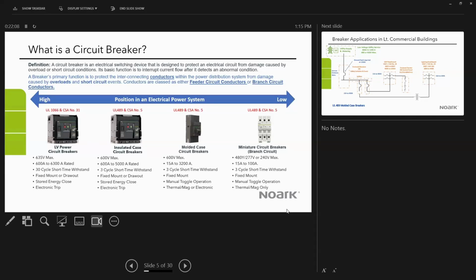number 31 in Canada. If I move on to the next breaker to the right, it looks very much like a low voltage circuit breaker. And in fact, it is the same construction, but it's a breaker that's been tested to the molded case breaker standards, which is UL 489 and CSA number 5. And the reason for having the same type of breaker with different ratings is because a molded case circuit breaker, or in this case, an insulated case circuit breaker, is intended to provide protection at that next layer of the power distribution system below the power circuit breakers.